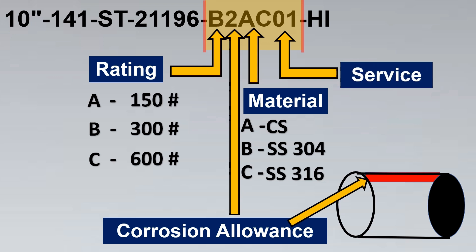This digit last in the end usually stands for service. For example C01 might stand for caustic service. So special precautions have to be taken with respect to material, with respect to coating. Then for example hydrogen services. So maybe certain hydrogen services require special cleaning, special type of materials that have to be selected. Gold plating needs to be done. So anything with respect to certain typical services is mentioned there. So certain precautionary measures have to be taken. NACE for example etc.